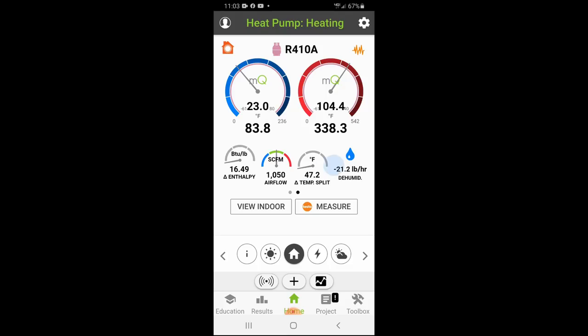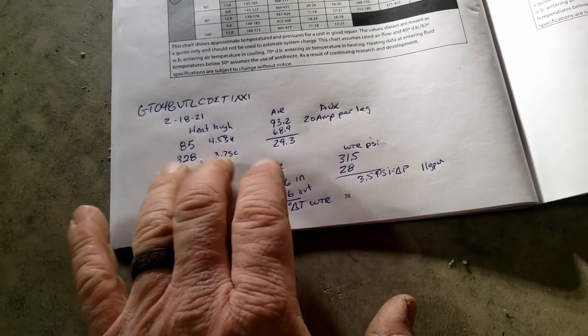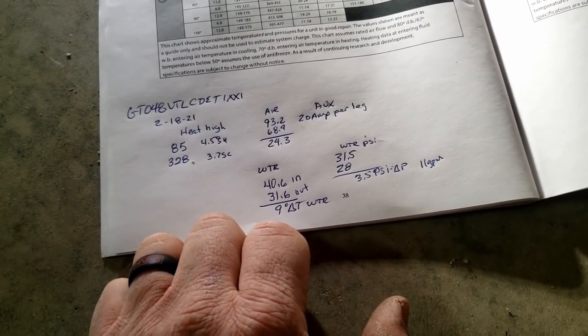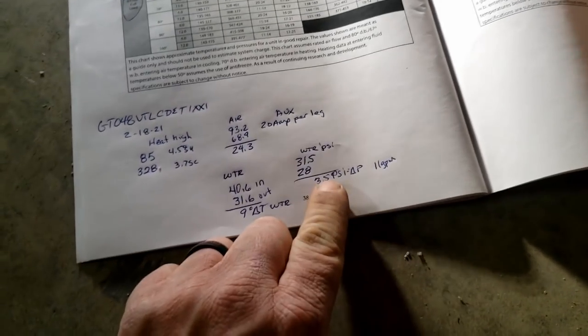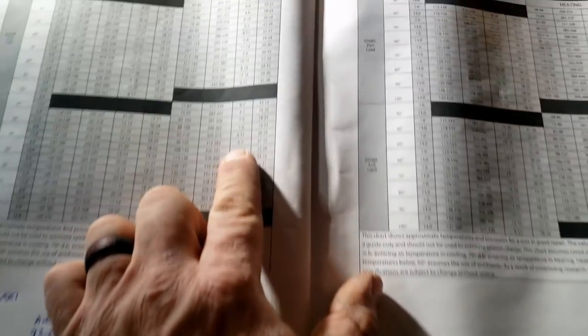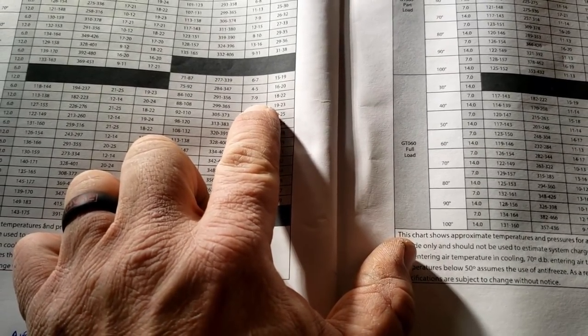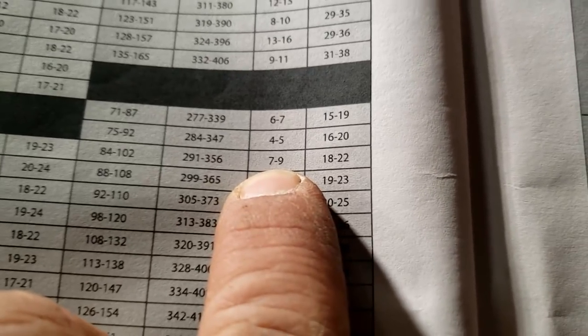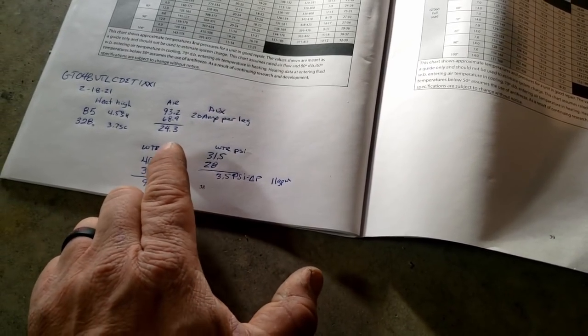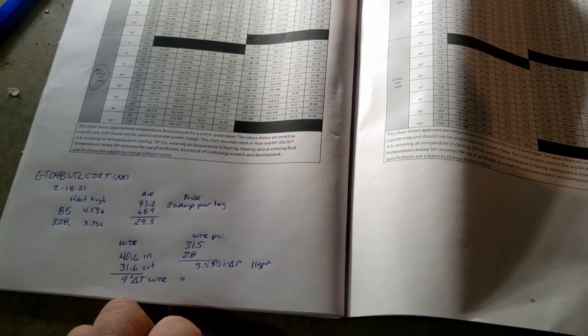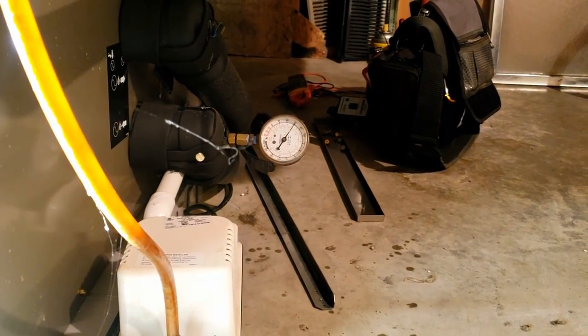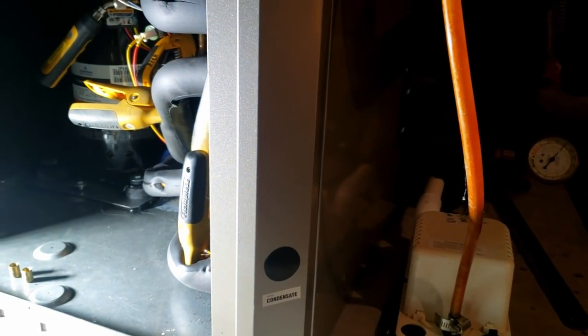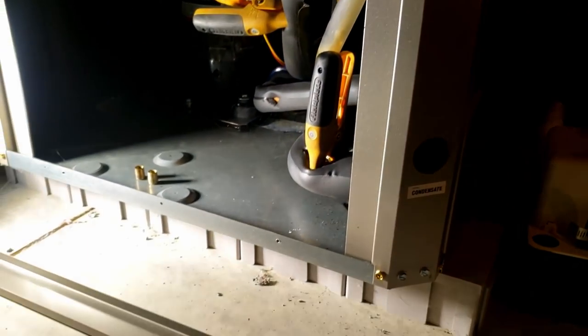Temperature split - the only reason why it's off now is because the auxiliary heat just came on. Our subcooling and superheat's not listed, but they look pretty much in common for what this unit runs. Water in and out we have a 9 degree delta and our pressure is about 3.5 which comes up to 11 gallons per minute. You come over to your chart over here at 40 degrees and you go to 12 gallons, you look at about 7.9, we're right at 9. Eighteen to twenty-two we're right at 24, so air and water temperature are right in line, which is how you generally check these out. Went ahead and got our pressures there on our loop - that's how we calculate gallons per minute.